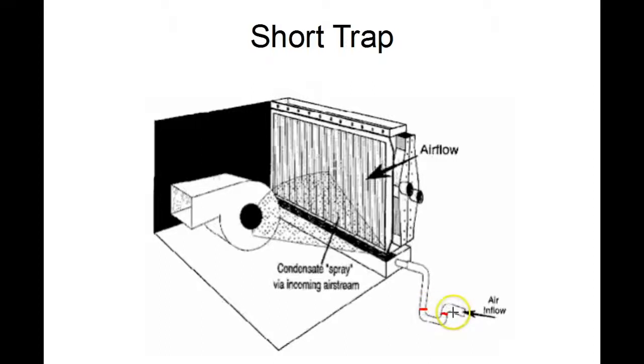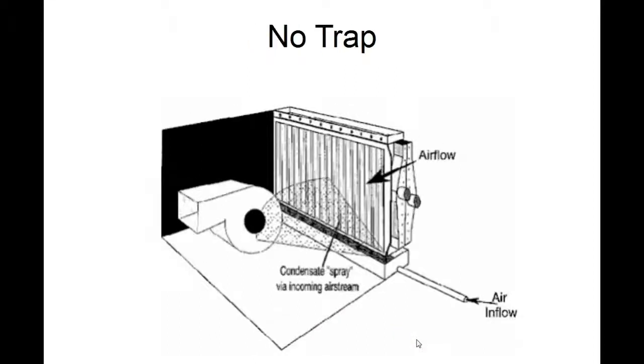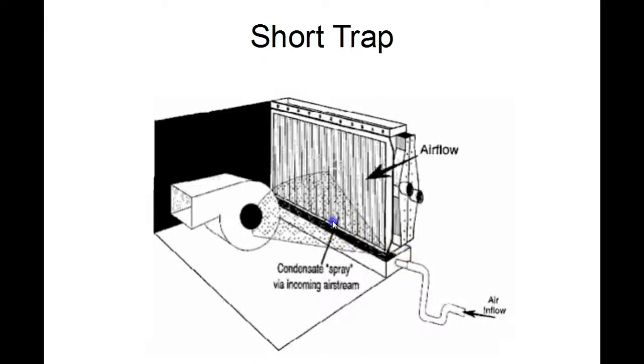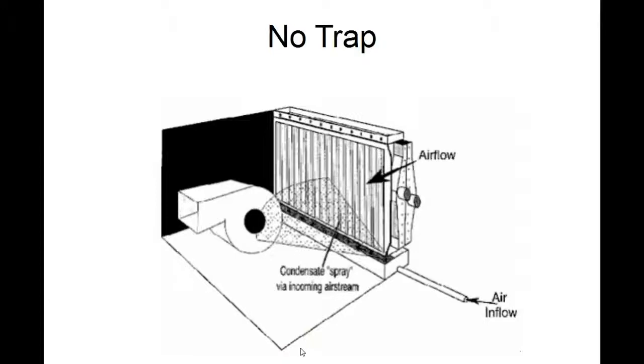When the unit starts up it will suck everything back up and the same thing happens with the short trap as with the no trap. You can see it creates the spray into the blower housing and into the ductwork. If the rise of this trap is shorter than the manufacturer's specifications for the unit, then it's exactly the same as not having a trap at all.